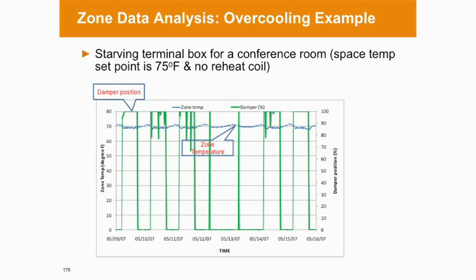So yeah, one thing we can think about, for example, like this kind of conference room, if we add up our occupancy sensor, motion sensor, whatever, so not only just control the lighting, if they can use relay, send a signal to the terminal box, let people know this is unoccupied. Then at that condition, you can write a code to program the minimum airflow set point to 0, because we know that there's nobody in this conference room. At that condition, they won't dump a lot of cold air to this space, so it won't be overcooling this space. So that's one thing you can think about, probably some programming work and some wiring work to control this kind of terminal box.